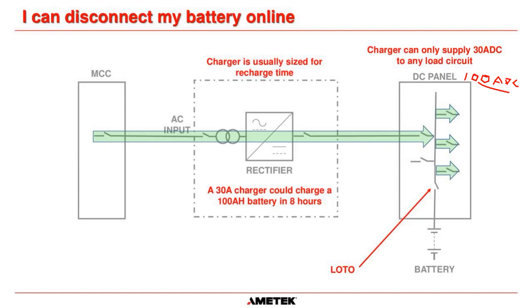Okay, that means they size the battery. Let's say we want 3-hour runtime. We want to size a battery that's going to give us 100 amps for 3 hours. So you choose whatever battery will give you that. Now for the charger, we're saying that a 30 amp charger is going to be fine to recharge that battery. But as John says, yes, you have to factor in that if the panel was pulling 100 amps, the charger can't supply all of that current on recharge.